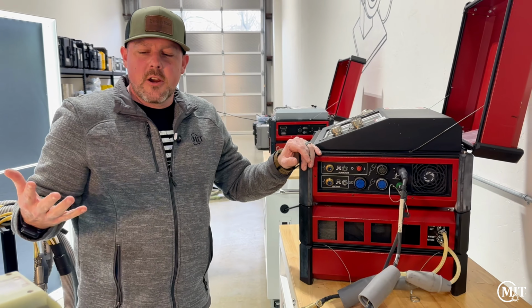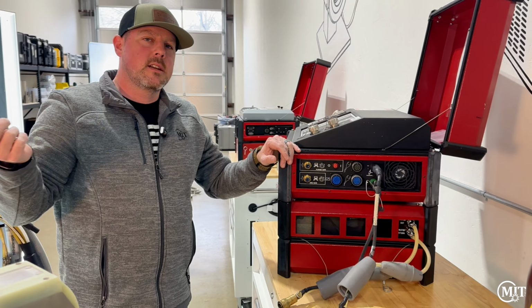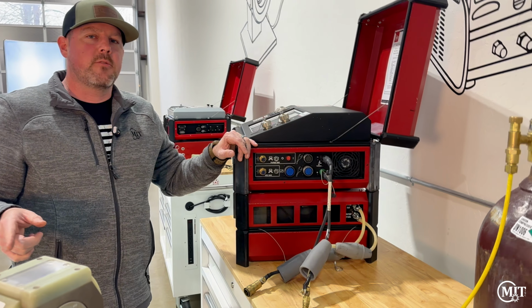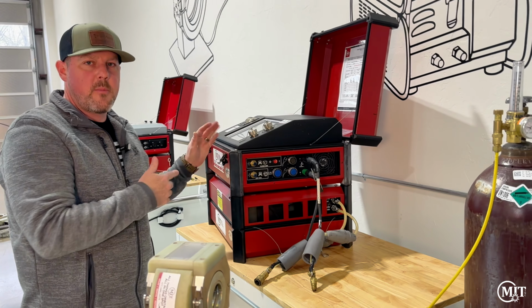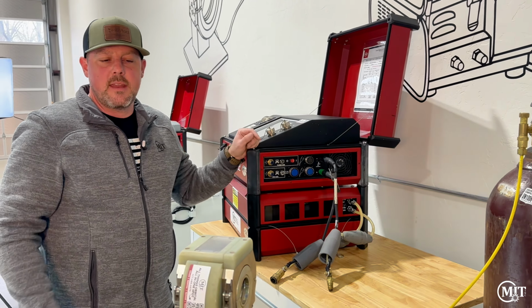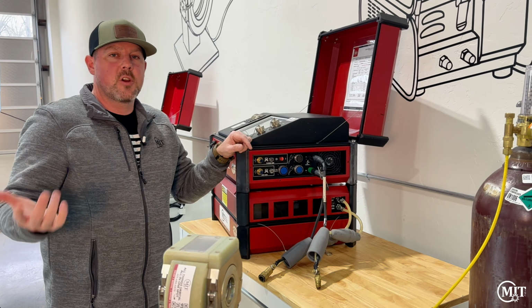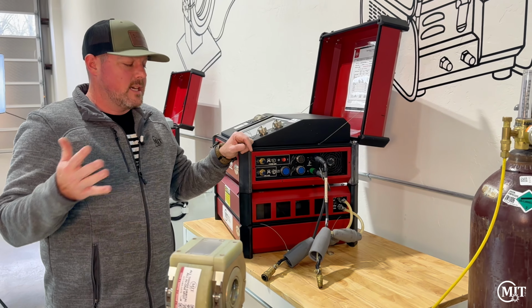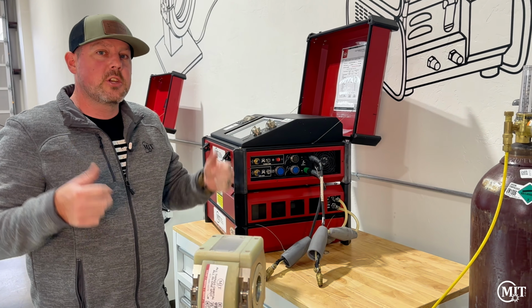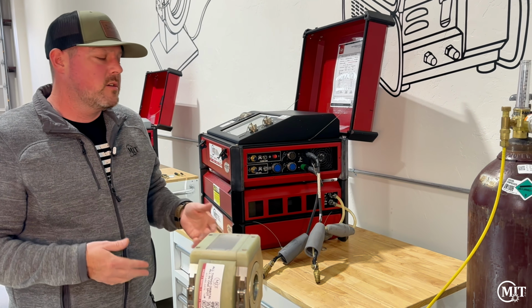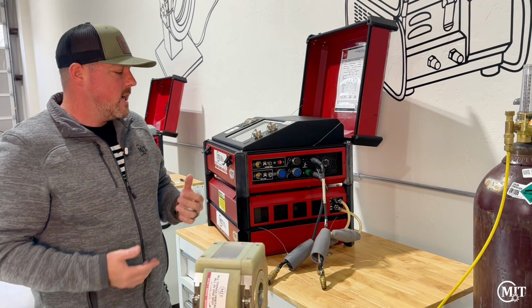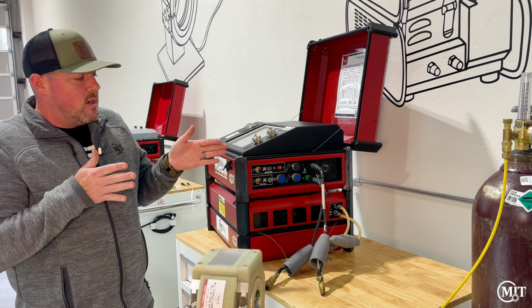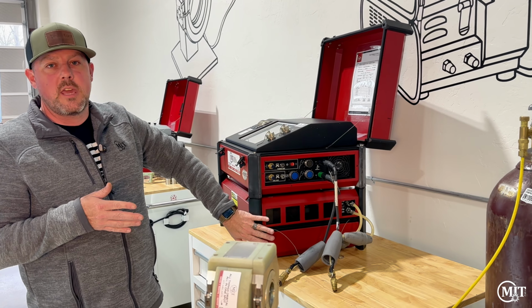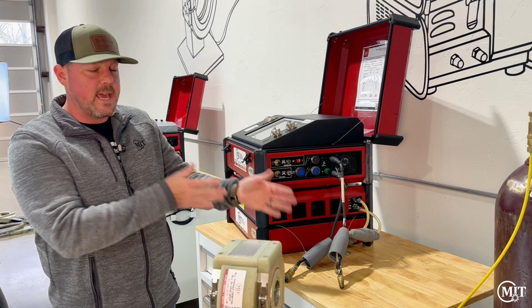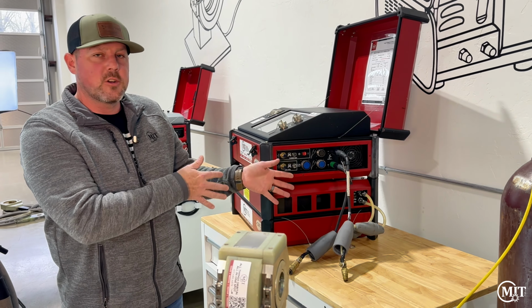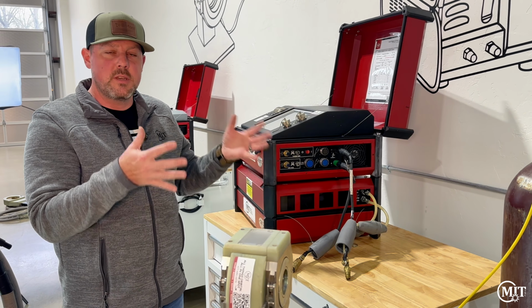So let's say there's a clog inside the line. Reversing the flow will try to push that clog out and potentially return it back to the reservoir, which might work. But let's say it doesn't work. Then we need to figure out: the cooler itself is working, we know that, our connections are good, we've reversed the lines, and we still have a clog.